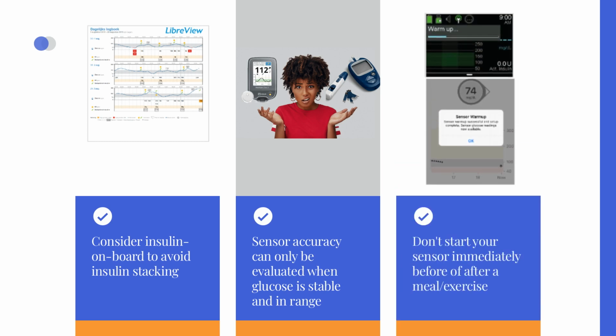Most sensors are calibrated at the factory, but they need a warm-up period of 1 to 2 hours before they start displaying glucose values. If there are significant fluctuations in sensor glucose during this warm-up period, the sensor's data may contain errors. Consequently, it's wise to replace your sensor at a time when you anticipate stable blood glucose levels, not immediately before or after a meal.